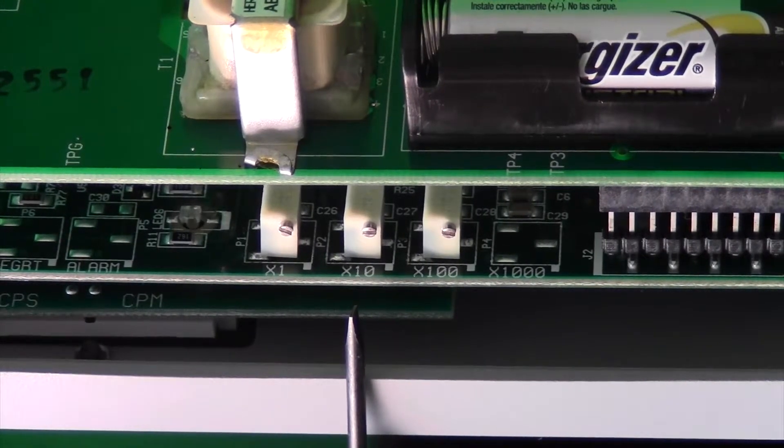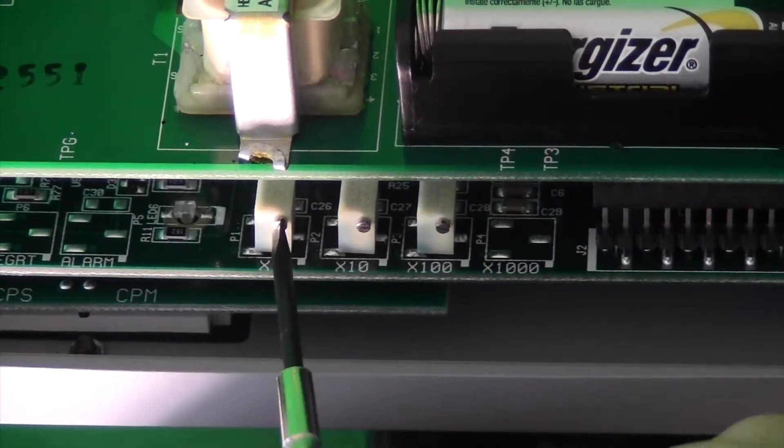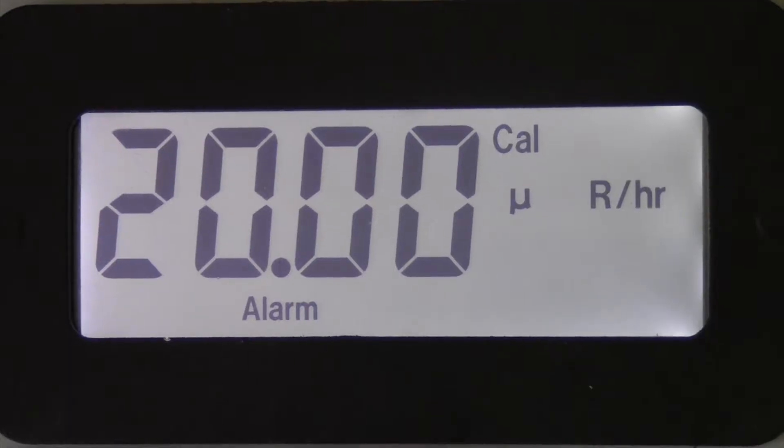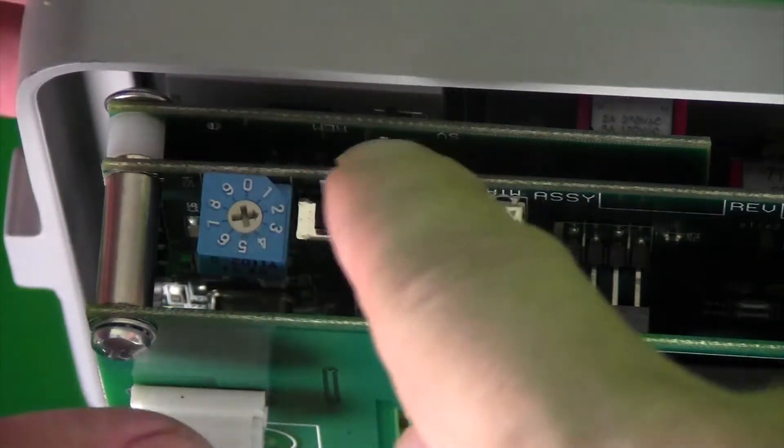Set with a screwdriver to desired set alarm rate. This time, it's 20 microroentgen per hour. Press the black button SW5 again. Turn the blue switch SW4 back to zero.